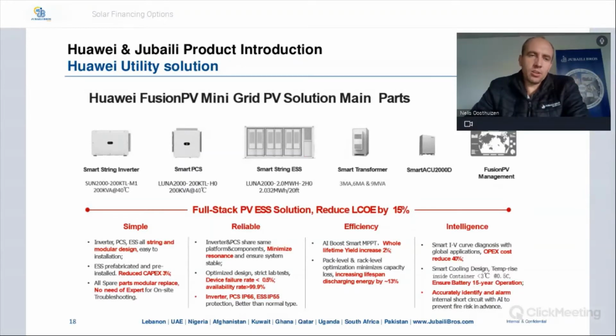So we do get it a lot where customers would like to use a 200 kTL inverter on smaller projects, but then because of the medium voltage output, you require a transformer station, and that can quickly escalate the costs of your whole system. So please bear in mind this 200 kTL option is actually only viable economically on bigger projects, more than 1 megawatt. In my personal experience, I would say not less than 3 megawatts. So if you have 3 megawatts or more, then you can go for the 200 kTL inverter.